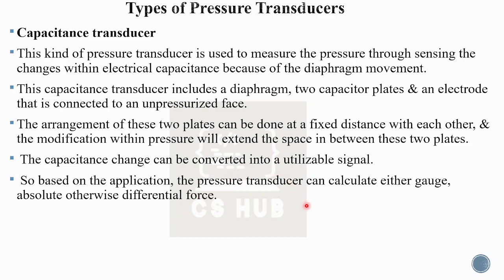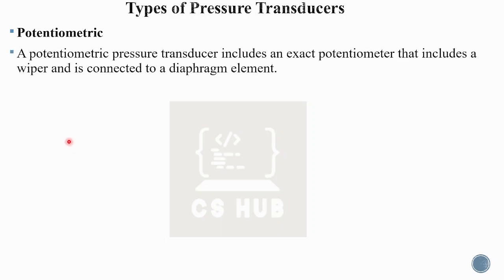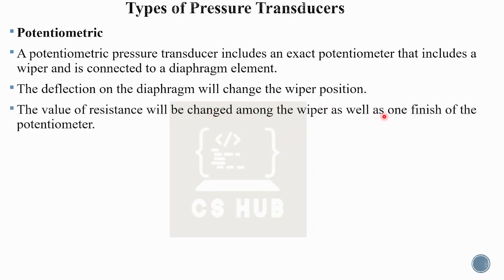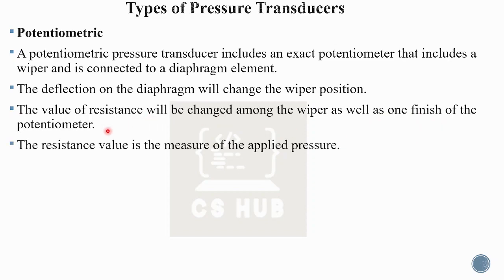Based on the application, a pressure transducer can measure either gauge, absolute, or differential pressure. The potentiometric transducer uses a potentiometer. The diaphragm deflection changes the wiper position. The wiper is connected to the diaphragm element. The deflection on the diaphragm changes the wiper position, and the value of resistance will change between the wiper and one end of the potentiometer. The resistance value is the measure of the applied pressure. When pressure is applied, the diaphragm moves, the movement is connected to the wiper, and the resistance changes.